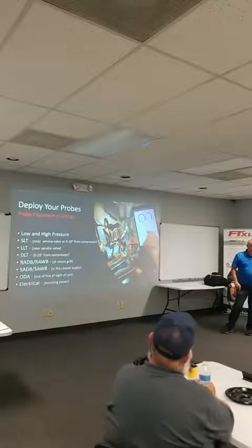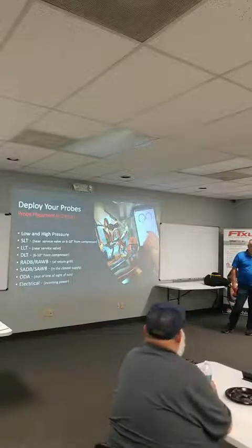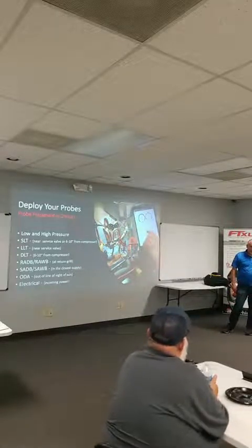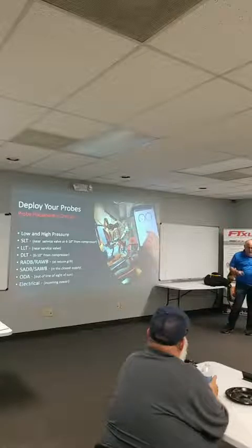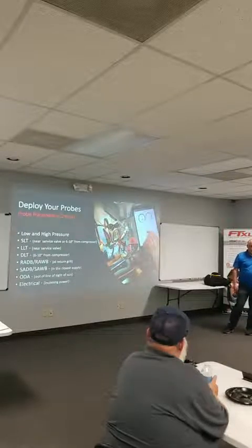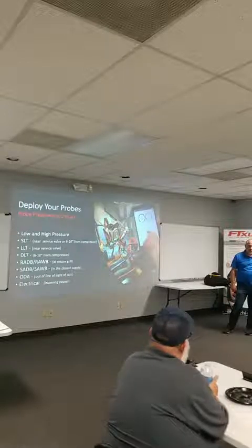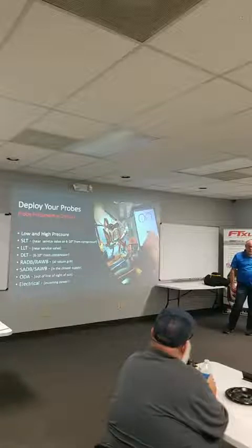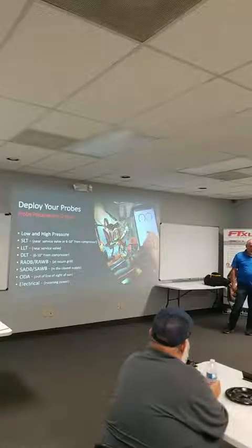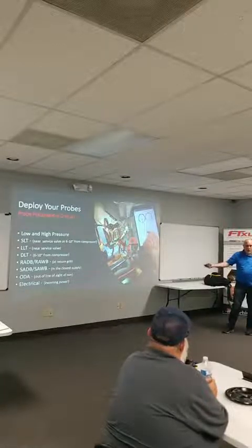A lot of guys, I had a guy tell me the other day, I'm like, dude, you cannot put your probe that close to the evaporator coil. And he's like, why not? He goes, here, you put it on the backside, he's measuring air going into the evaporator coil. I'm like, it's going to influence the temperature. He goes, oh, bullshit, the air's going this way. I'm like, dude, have you ever heard of radiation, right? Radiant cooling. Heat travels from hot to cold, period. Your hot probe is going to see that cold coil, and heat's going to travel right into that probe. Doesn't care which way the air is flowing. It's going to cool that probe off because it's next to it. Just like walking in a freezer aisle at Walmart, right?